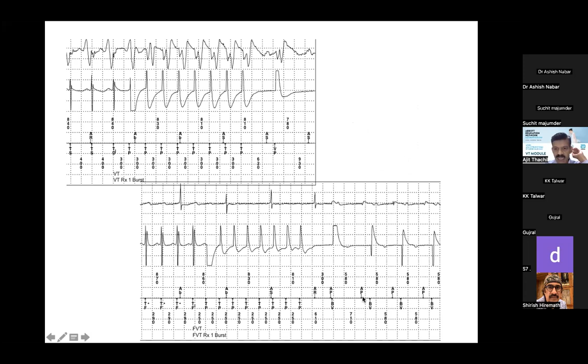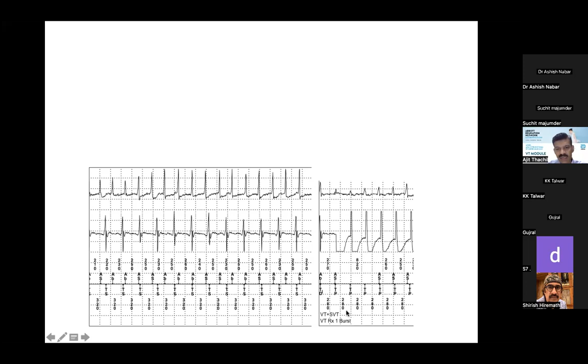Now, if you look here at this tachycardia, the atrial channel shows AS, AB. I'll shortly explain what AB is, but you can see that the atrial intervals are 210, 220, 210, 220, 230, 260. It is faster than the atrial tachycardia detection rate. That's programmed separately. All devices with an atrial channel have an atrial tachycardia detection rate, which is the AF detection rate. Because it is faster than that rate, it has detected an atrial tachyarrhythmia. But at the same time, it is also saying TS, TS, TS, TS, and then TD. So it has also detected a ventricular tachyarrhythmia. So finally, it says VT plus SVT: I have detected an atrial tachyarrhythmia as well as a ventricular tachyarrhythmia.